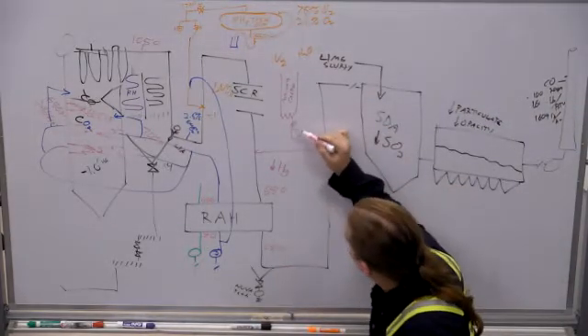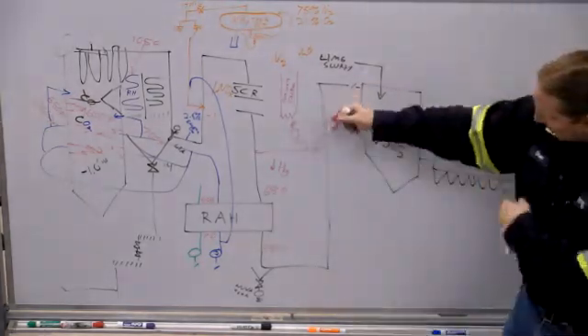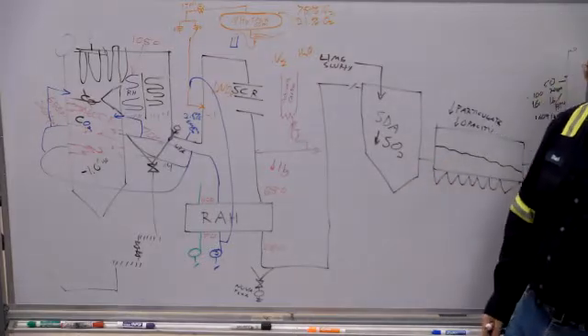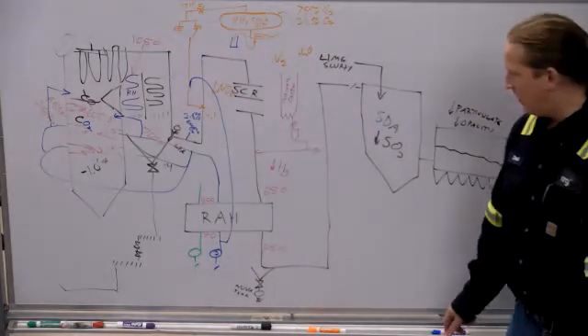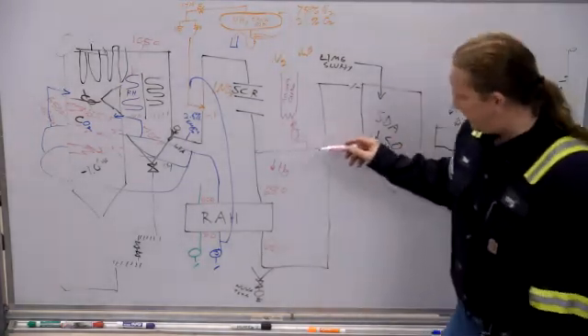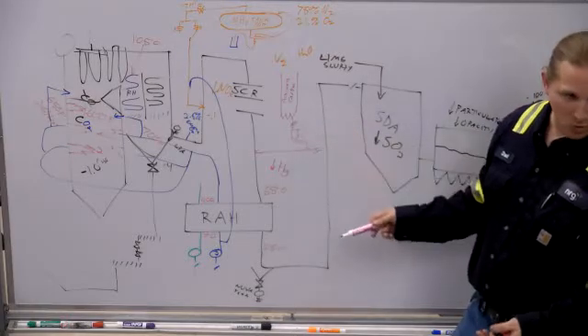So the hopper has a low-level switch on it and a high-level switch on it. Whenever the high-level switch clears, it tells the rotary feeder to run, and it catches it and dumps it in. And once the high level comes back in, it runs for another 15 seconds or something, and then stops. And that way you're batch filling that little hopper on top all the time. That low level switch comes in, and it shuts the blower down and the screw feeder down. And that is because we're done transferring. When this whole system gets empty, then that stuff likes to flow like water.